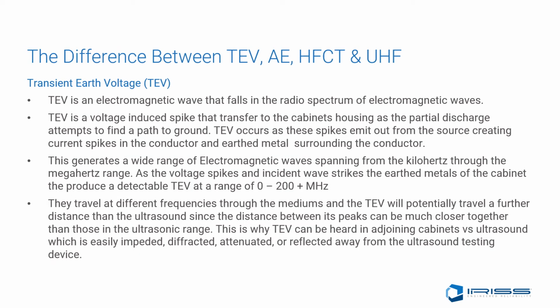The differences between TEV versus AE, better known as ultrasound, HFCT, and UHF. TEV stands for Transient Earth Voltage. TEV is an electromagnetic wave that falls in the radio spectrum of the electromagnetic wave spectrum. TEV is a voltage-induced spike that transfers to the cabinet's housing as a partial discharge attempts to find a path to ground. TEV occurs as these spikes emit out from the source, creating current spikes in the conductor and earthed metal surrounding those conductors.